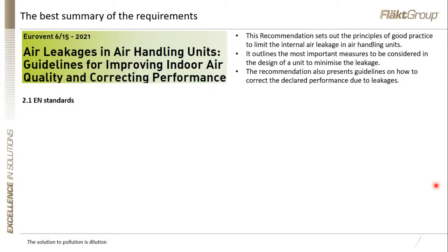There is a document, it's published by Eurovent, and it's the best summary to my way of thinking about how to improve indoor air quality and correct performance in air handling units by combating air leakage. And as you can see here, these are the objectives that were set out by the guide: good practice to limit internal air leakages, outlines important measures to be considered in designing the unit to minimise leakage, and the recommendation also presents guidelines on how to correct the declared performance due to the leakages.